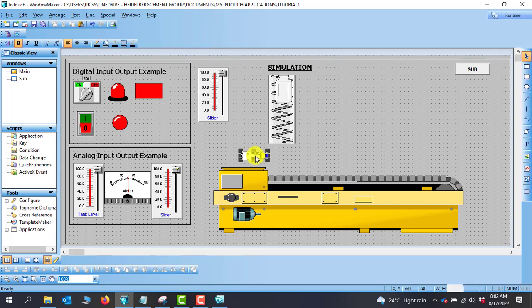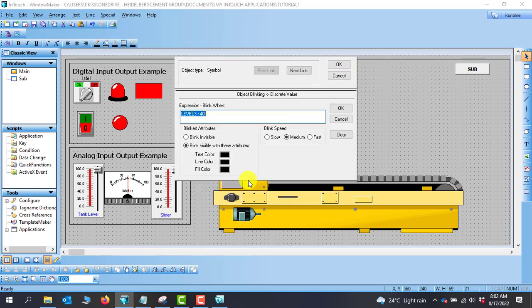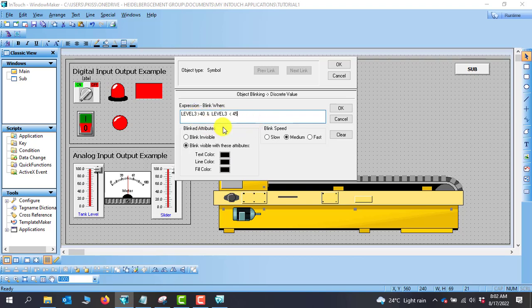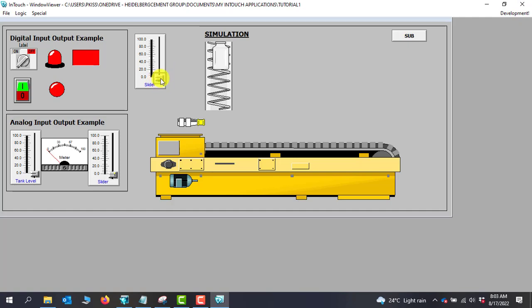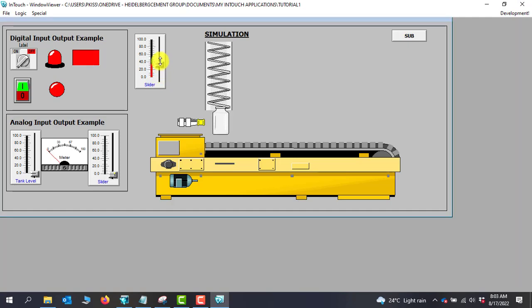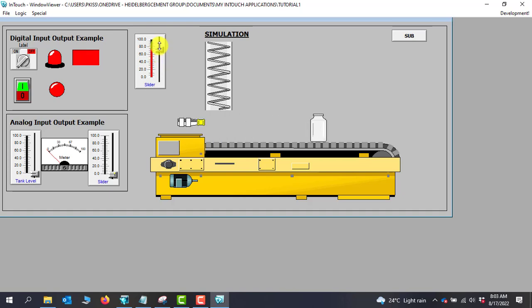We go back and add more conditions to the blink expression. The sensor should only blink when the level is within range: Level greater than 40 AND Level less than 45. Within that range of 40 to 45 we know we are within the sensor's detection range, and when we move away the blinking stops. Going to runtime, immediately we are in range blinking starts, and when we move away it stops.